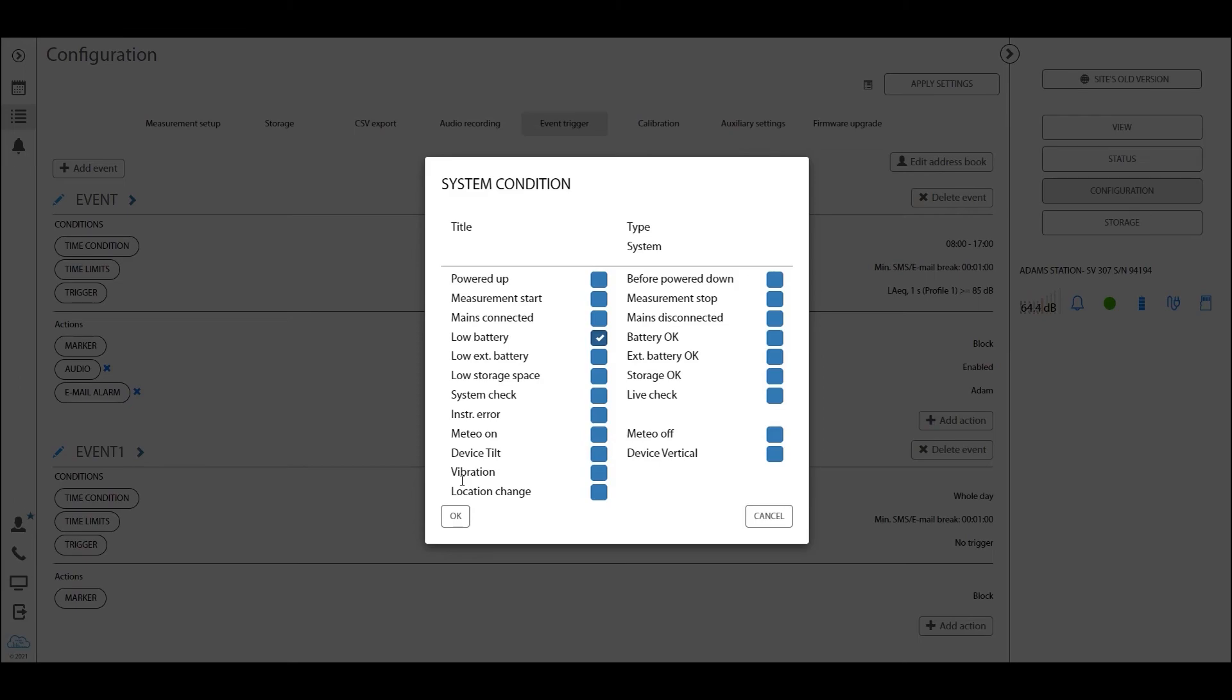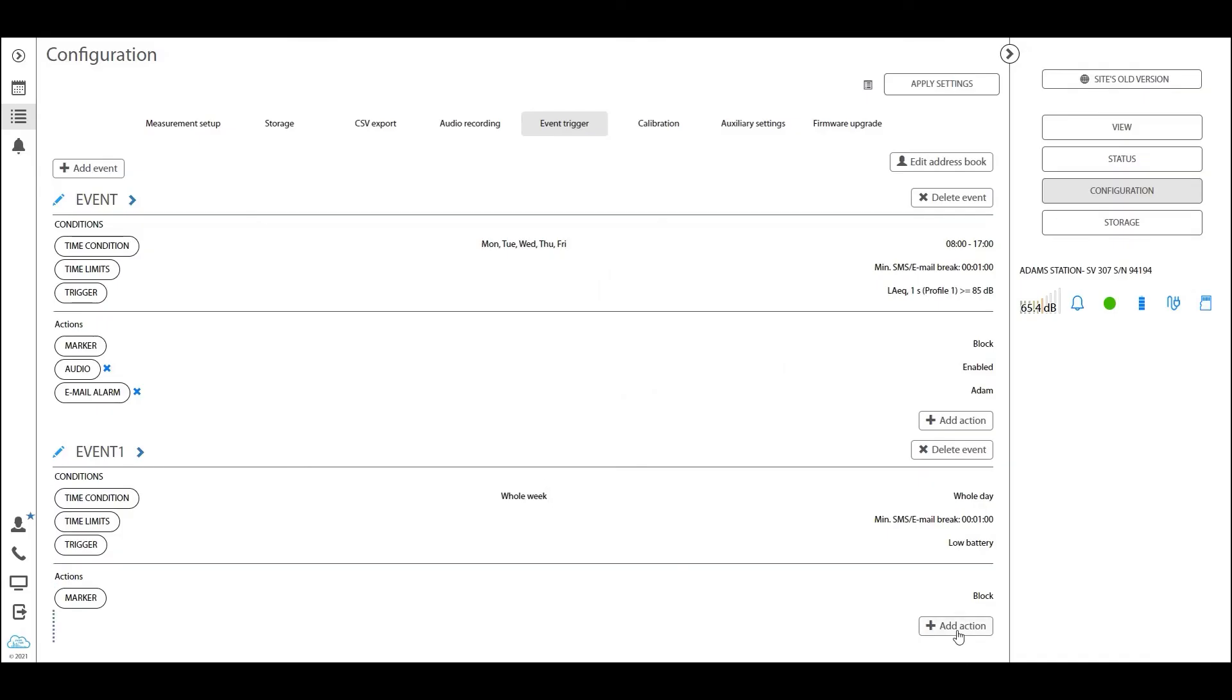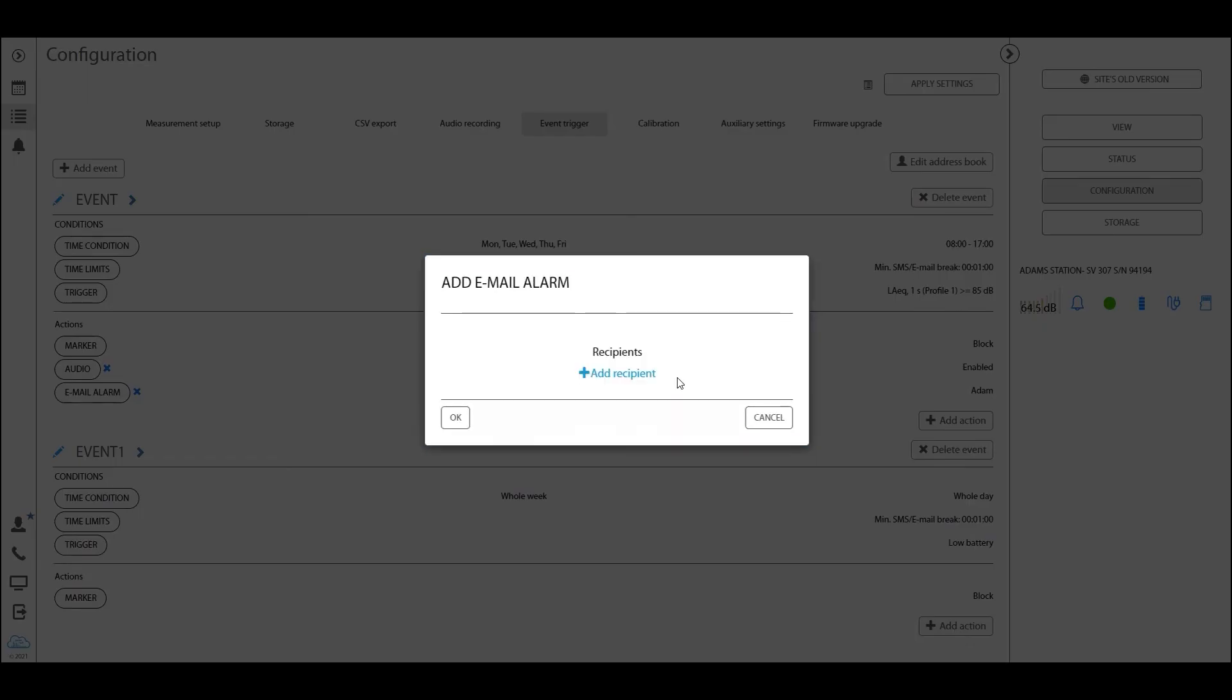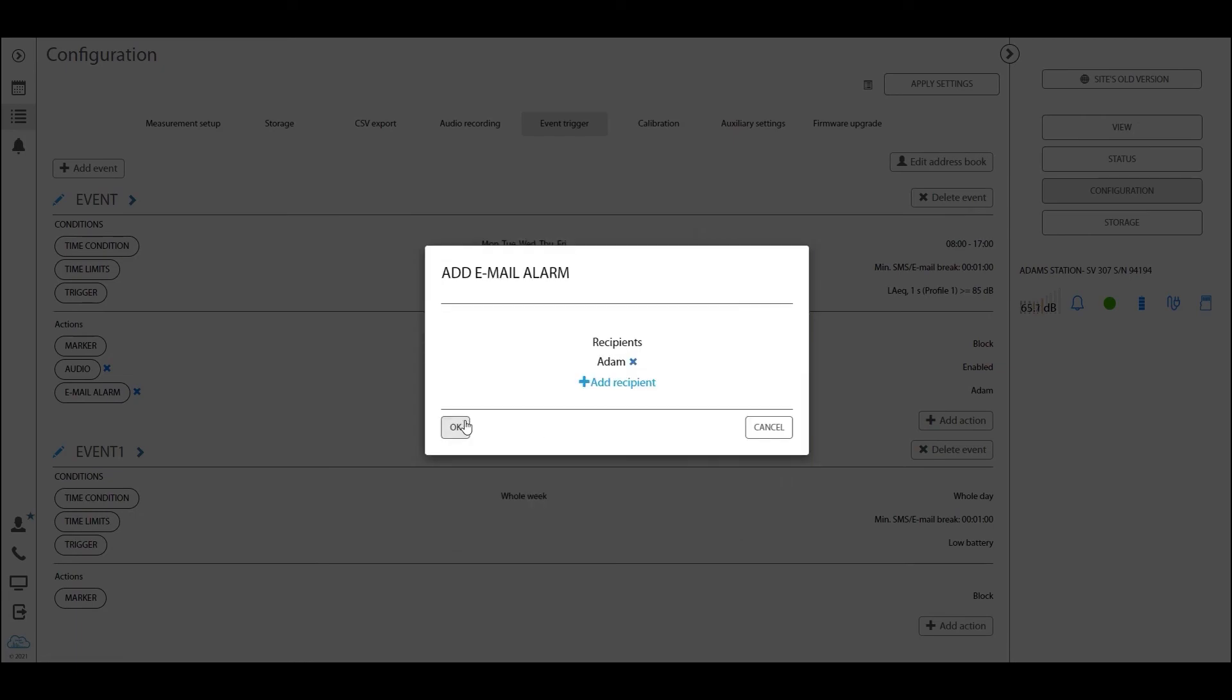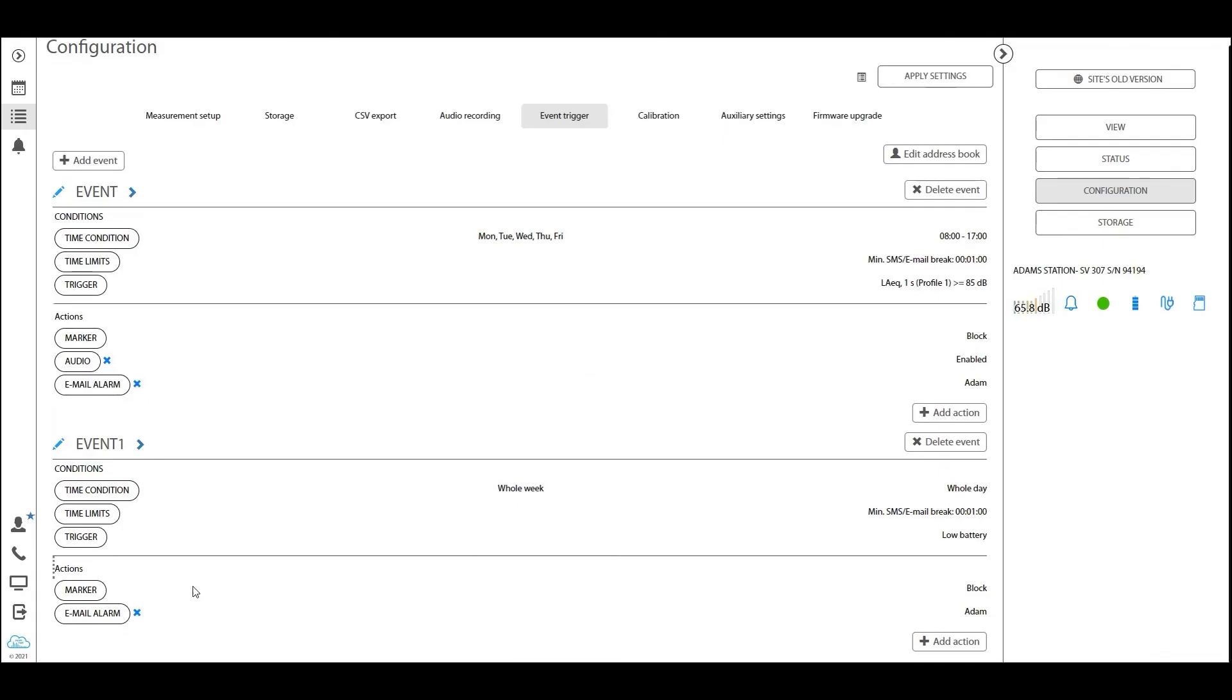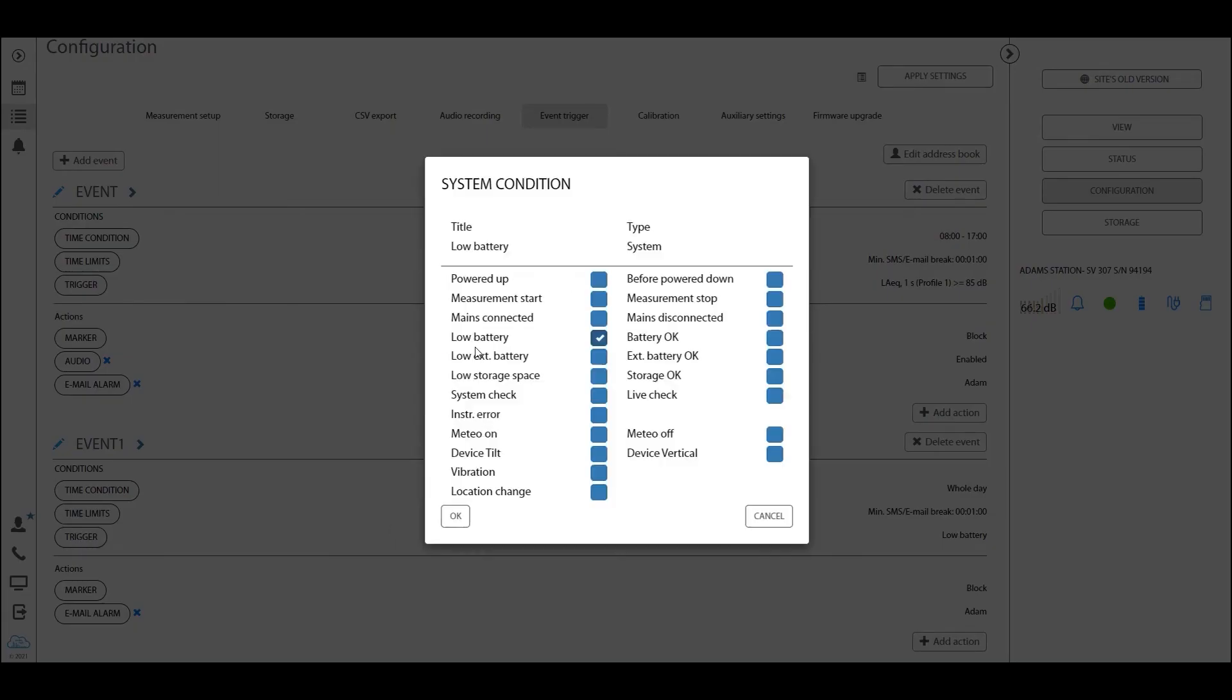Now one that you would expect for sure is, for example, the low battery one. So what does it mean if we set this to okay and then we set action as an email alarm to Adam as we did before? This would indicate that when the battery inside the instrument is lower than 10%, this will send out an alarm to Adam via an email.